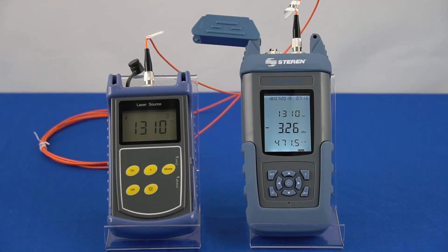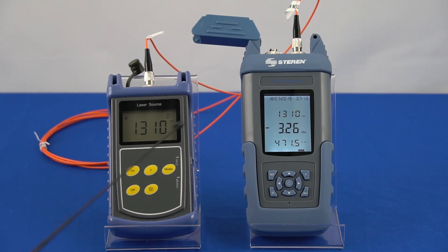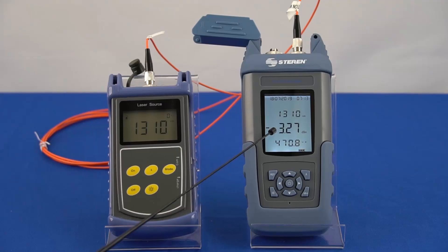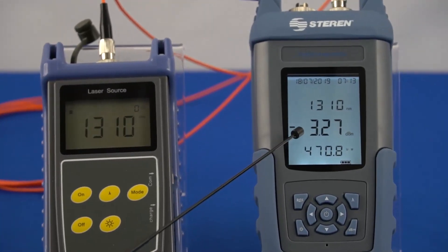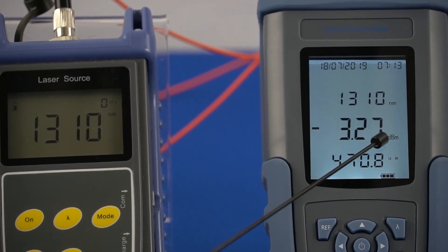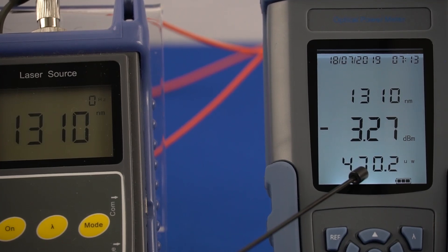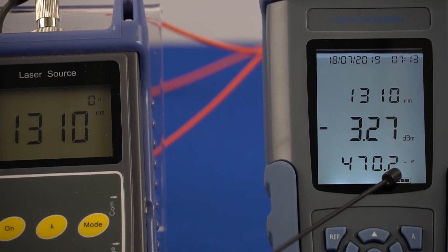Verify that the power measurement on the optical power meter meets your power level from the source. In this case, our laser light source outputs around negative 3.27 dBm, which is equivalent to 470 microwatts.